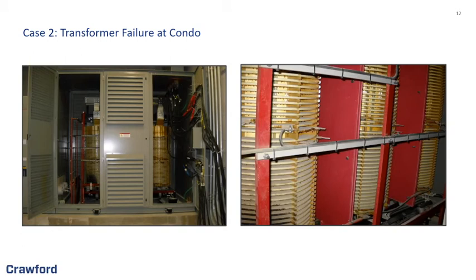It wasn't for backup purposes, and that was costing $14,000 per day for the rental and the diesel fuel it burned. If you recall, the hospital was $20,000 a month. This was $14,000 a day. So we've got much more significant exposure. Again, we retained an electrical engineer to assist us in determining the cause, which was determined to be a surge from the hydro supplier's equipment. So really no other outside interference, no lightning, no water involved. So we have, again, a pure equipment breakdown loss, where the equipment breakdown policy was the only one that was going to respond.